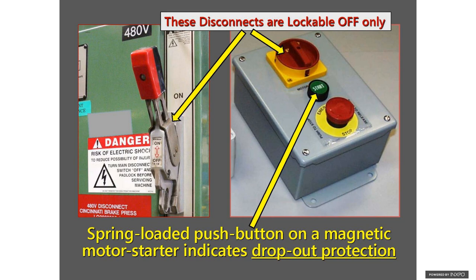Disconnects need to be lockable only in the off position, whether it's a rotary-type disconnect switch like the one on the right or a flange-type disconnect switch like the one on the left. We just talked about the red emergency stop features. And on the left-hand side with the flange-type disconnect, the holes line up when you're in the down or off position, at which point you can place a lock or lockout tag up.